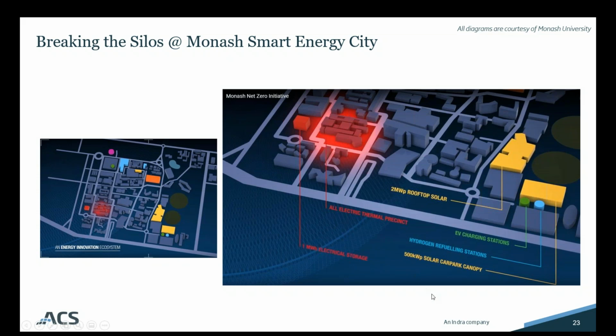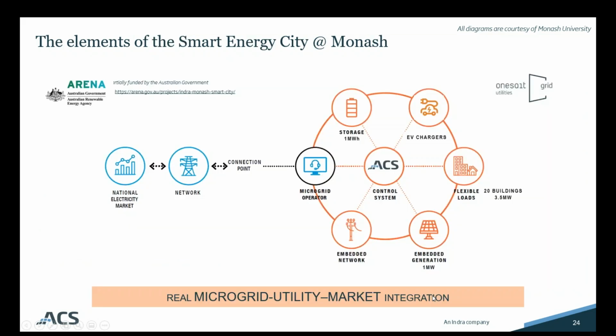The coordination of several loads, such as 20 buildings and an EV charging infrastructure, of solar PV installation and 1 megawatt-hour of energy storage, is performed through the hybrid, that means centralized and distributed, platform, Insight AGM. Each load, source, or controllable grid device is connected to an intelligent IIoT processing node, pretty much like our colleague John was indicating before. This node continuously processes data to analyze local power quality issues and to perform control actions to prevent the escalation of any negative effect. There's a centralized platform that executes the coordination of more nodes, dispatching control commands.